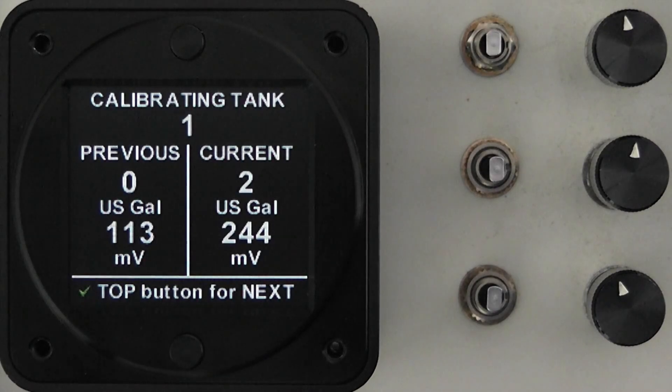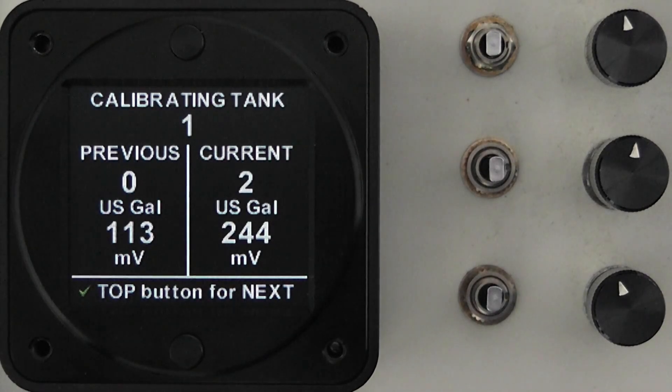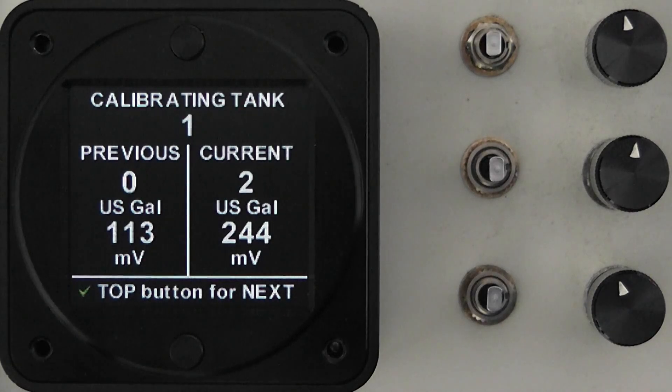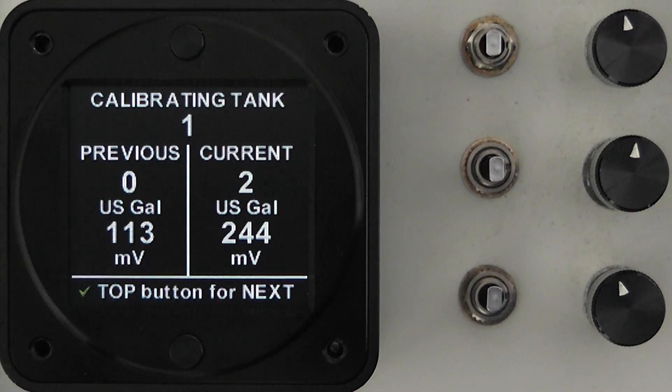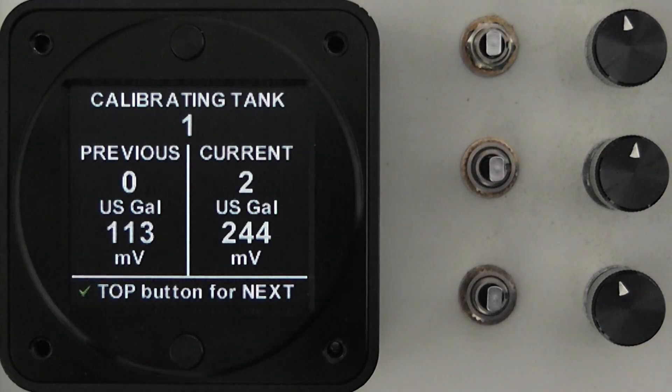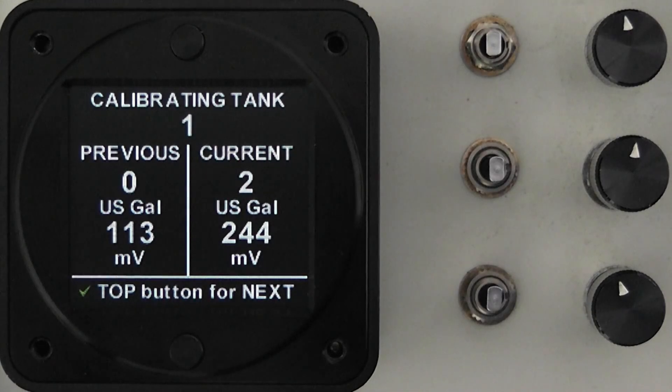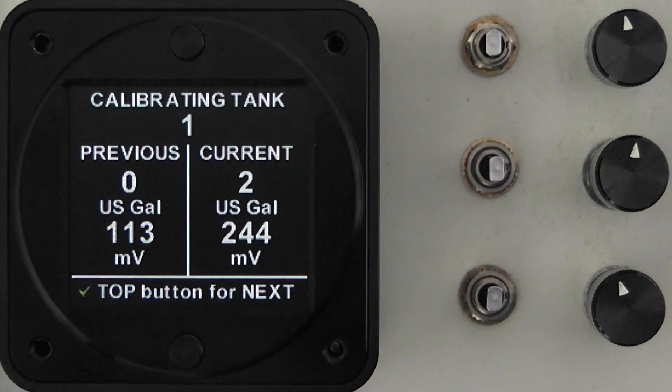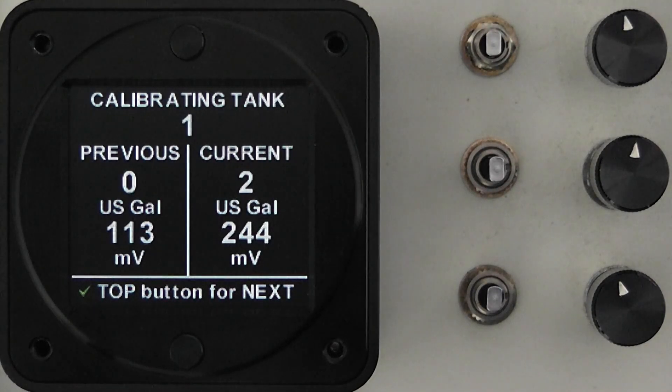If that tick mark is red at any point in time your sender resistance has not moved in the correct direction or not changed at all and the calibration of the instrument you will not be able to go to the next step you will just be able to exit and save what you have done this far.